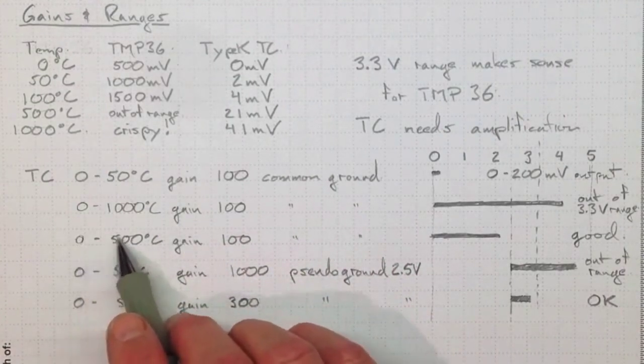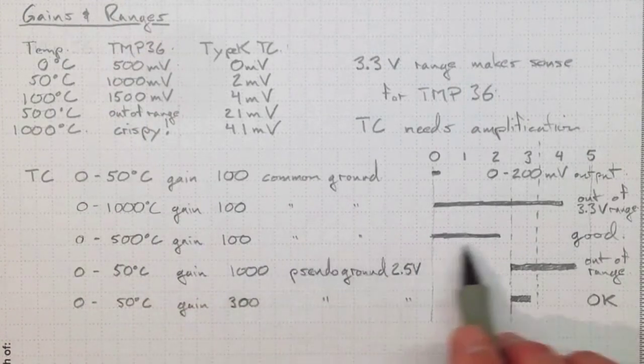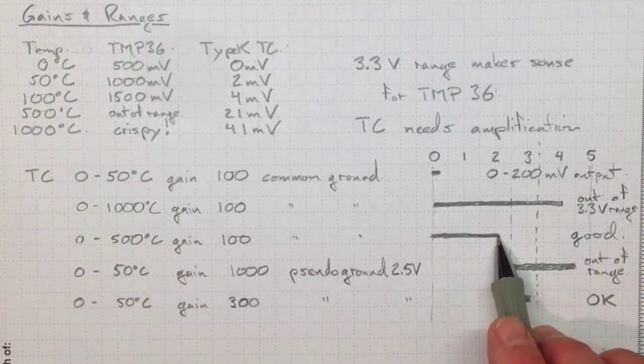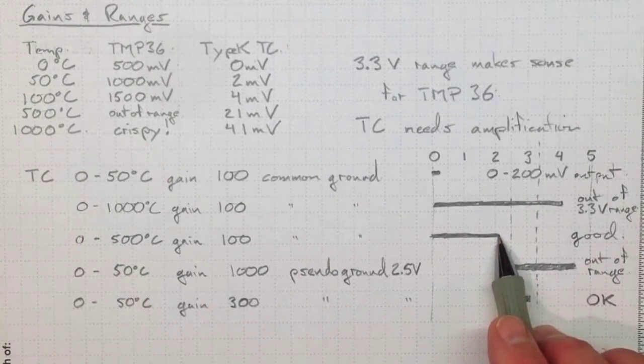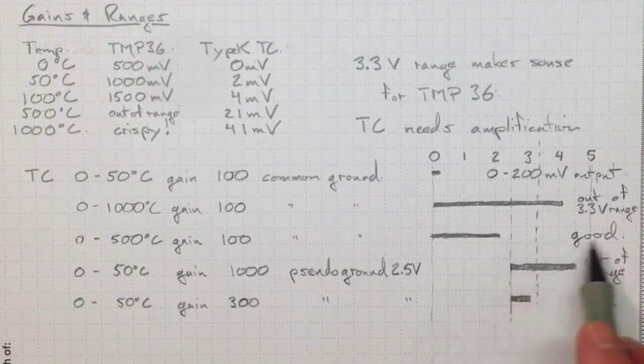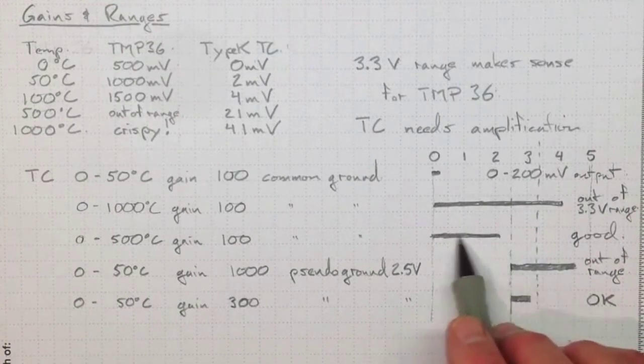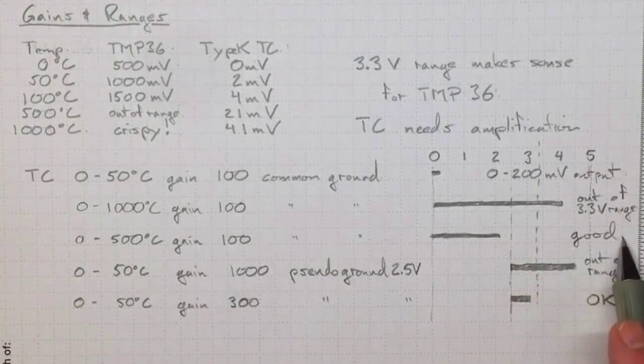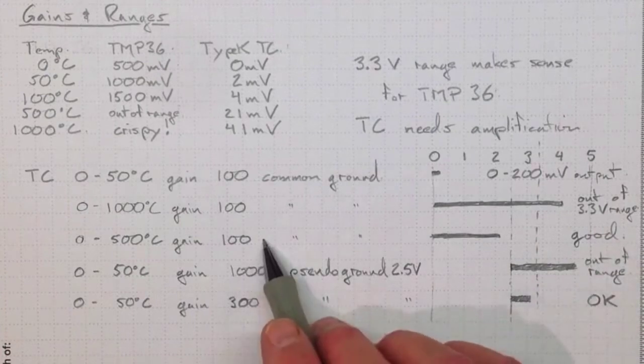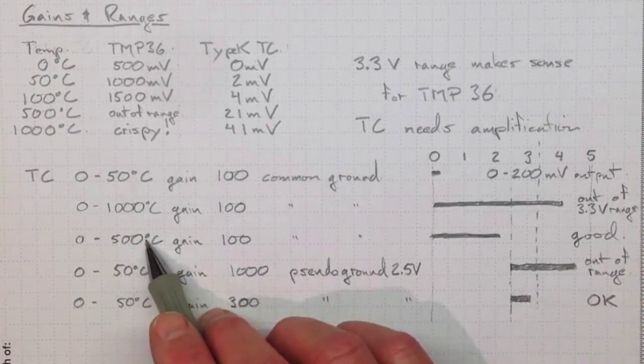If we were looking at zero to five hundred degrees C with a gain of one hundred, that would work just fine. We'd get up to a little over two volts input. We'd be making good use of the range - we're using about two-thirds of our range in there, so that's giving us good resolution. That's a good choice for measuring zero to five hundred degrees Celsius.